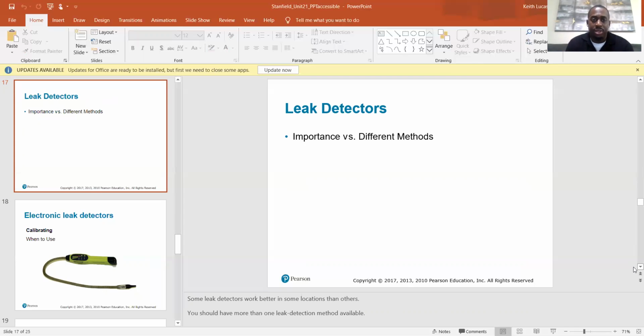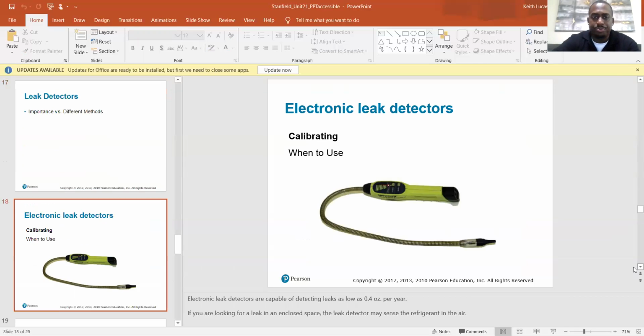So I let it continue to evacuate while we did other little odds and ends. Once we were done, I got that thing to 300 microns. So I know some of y'all can appreciate that. It was a good day. So anyway, leak detectors, importance versus different methods. Some leak detectors work better in some locations than others. You should have more than one leak detection method available.